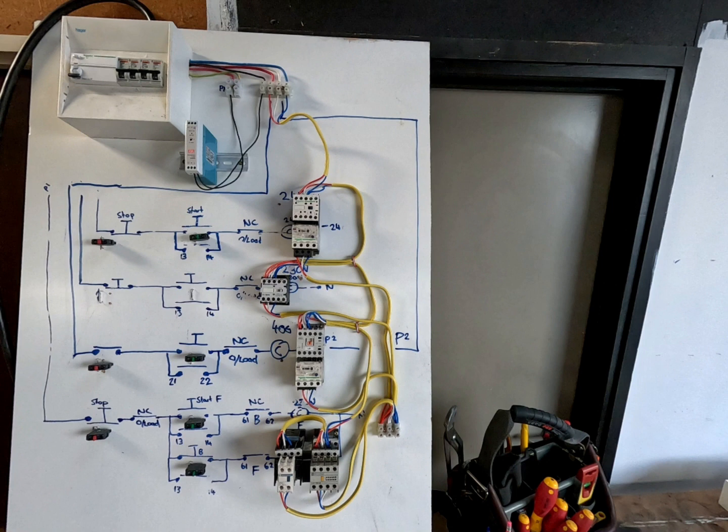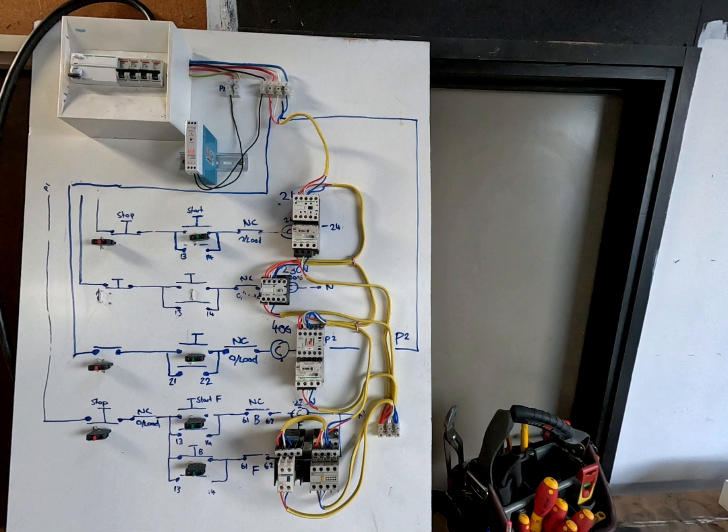So this is where I stitched myself up. A backstory: using a bunch of secondhand contactors that we've got in stock. 21 and 22 is a normally closed contact, which is what I said, but I needed a normally open contact. So later on in the video I find a different contactor that has a normally open and replace it with that.